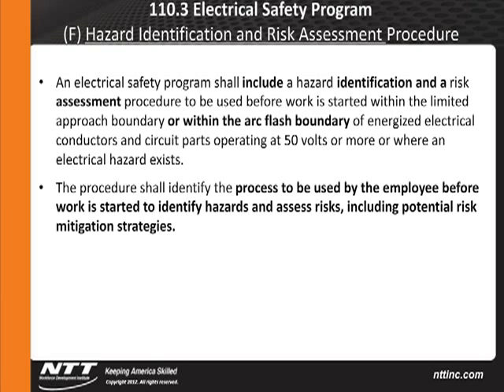Prior to that, the limited approach boundary was based upon an exposed part and piece. And for systems of 750 volts and below, that was basically 3 feet 6 inches. But when they added this language, or within the arc flash boundary, I've been at some of your facilities. I've seen arc flash boundaries in some cases that are 20, 30, 40 feet away. That is, again, going to change the way you have to do business. The procedure shall identify the process to be used by the employees before the work is started to identify hazards and assess risk, including potential risk mitigation strategies.